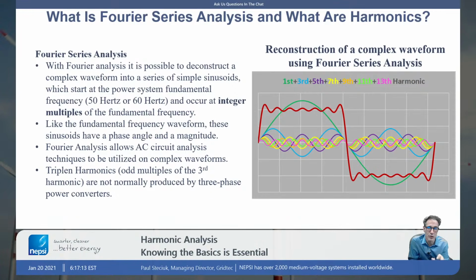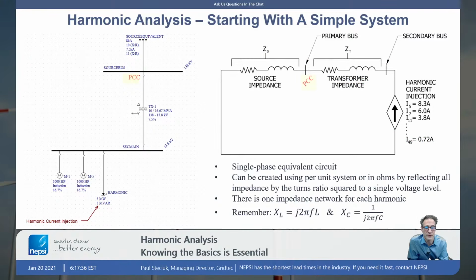So obviously one calculation may involve 50 calculations when you do harmonic analysis. If we're evaluating the harmonic response of a network and we're going to the 50th harmonic, it's going to be 50 sets of calculations that we must do to evaluate the harmonics in that system. So we're going to continue on with this subject matter.